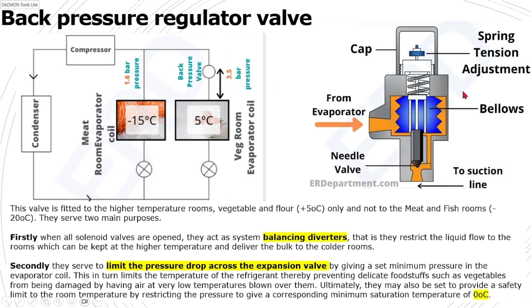This is actually a spring-loaded valve. As shown in the diagram on the right-hand side, it simply holds a pressure. The refrigerant gas coming out of the evaporator cannot easily pass through — it has a barrier. So it holds back some pressure, causing the evaporator pressure to increase. As the evaporator pressure increases, the saturation temperature also increases.